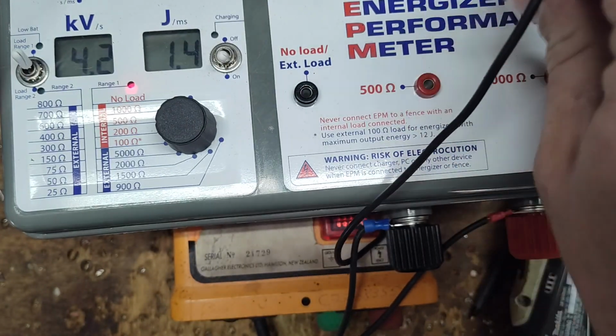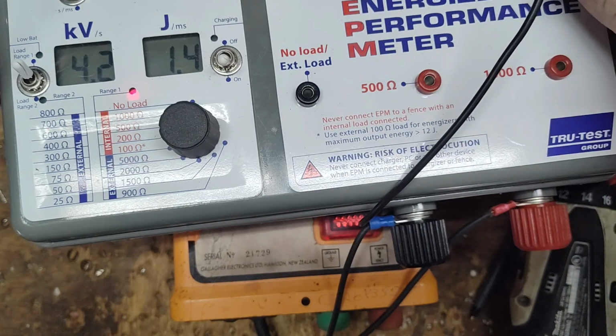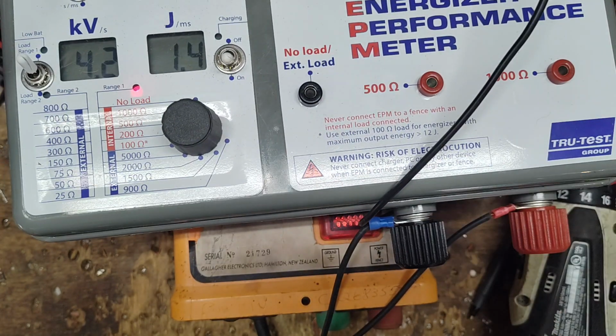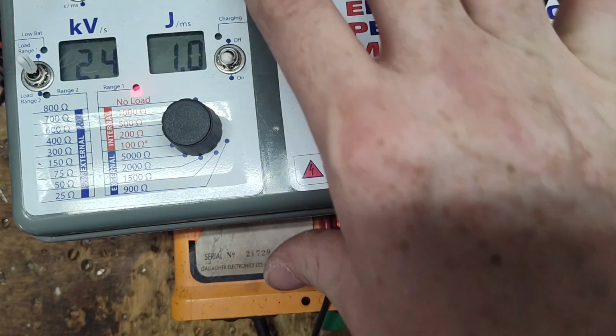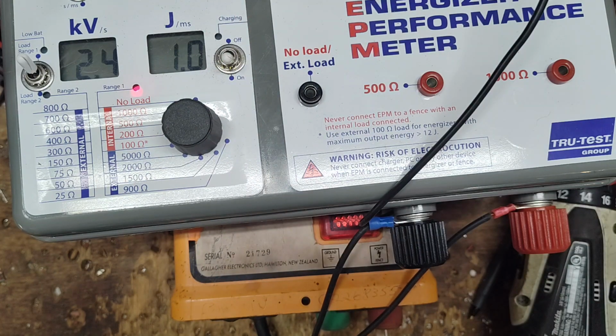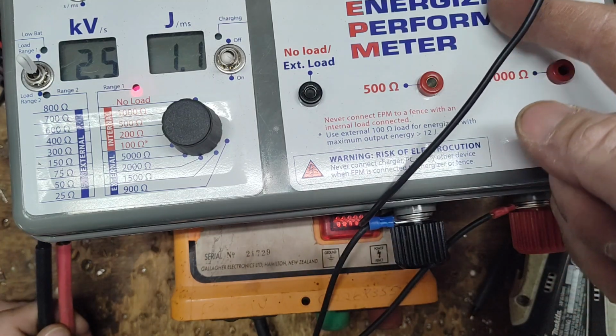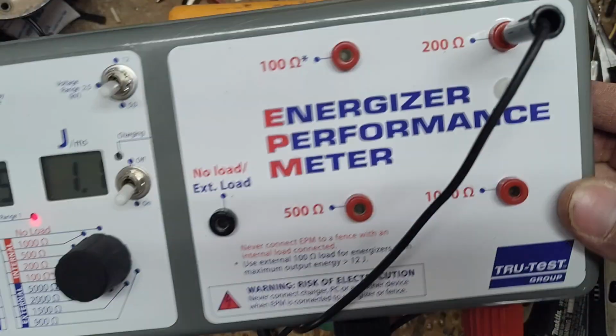We'll drop it down to 200 ohms. This is a pretty hard load for such a small joule unit, so I don't know where it's going to level out at. We're at 2.5 kV at 1 joule. Let's drop our voltage range down a little bit, see if we can get a finer reading. Nope. Drop it down one more time. It didn't change too much. 2.5 kV. So somewhere between a 500 and 200 ohm load on there.